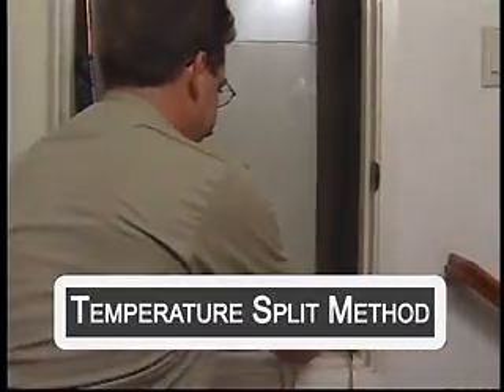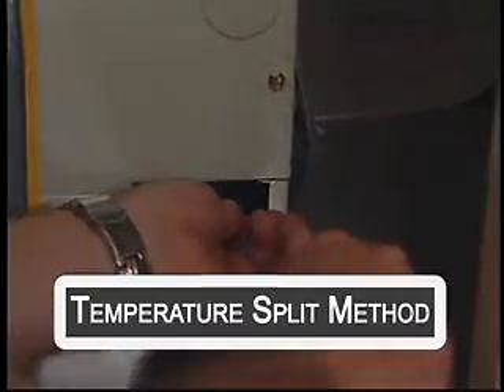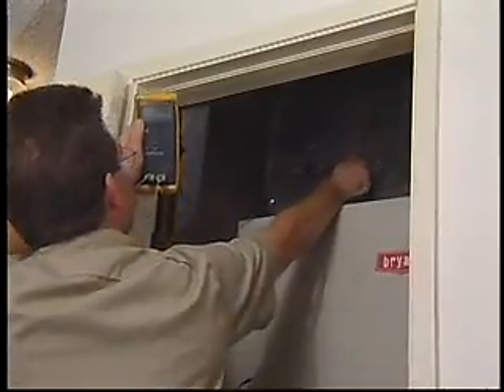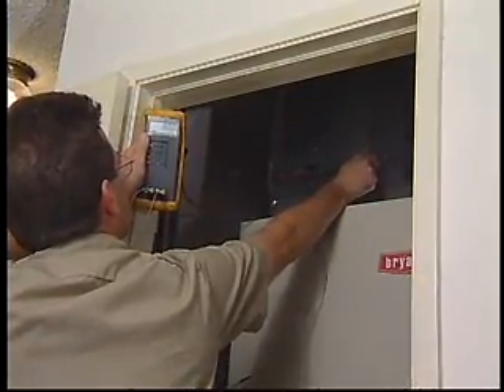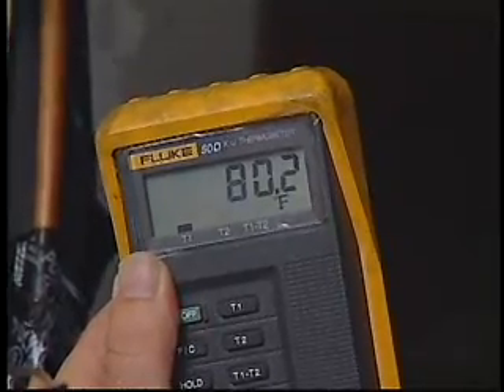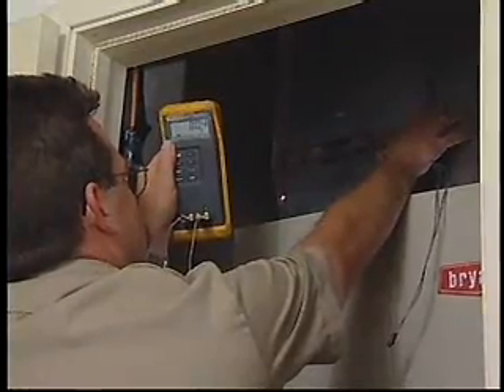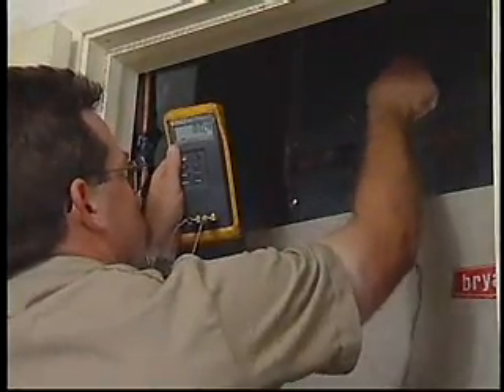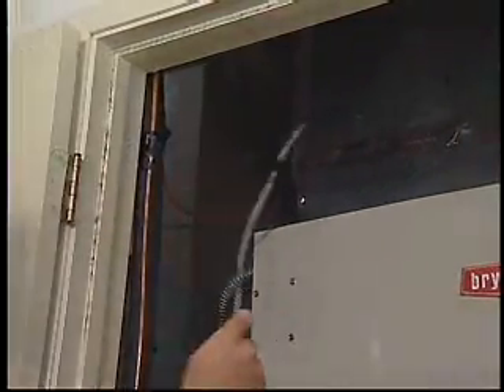There's a couple of different ways of testing it. There's a temperature split method, which is a real common method. It's easy to do. What you do is you measure the wet bulb and dry bulb temperatures. That tells you what the humidity is, as well as the temperature on the return side, and also what the temperature is on the supply side. So you see how much the temperatures drop between the return and the supply. And based on that temperature drop, you can tell whether or not you've got too little airflow.